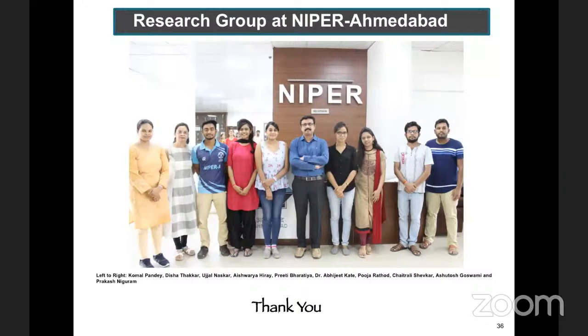Calibration is very important for this particular instrument, especially in terms of mass accuracy. If you have a time of flight instrument, then generally we do calibration every day, because temperature also creates some kind of disturbance, and this is very important. Calibration is nothing but, in mass spec, we call it tuning.